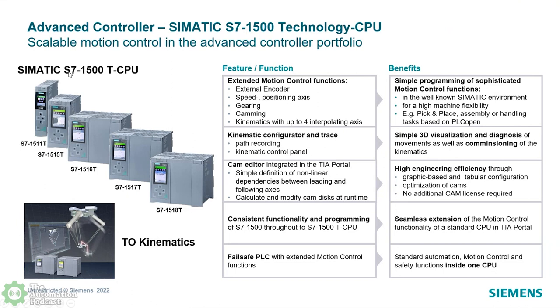For anybody new to Siemens: the CPUs actually get faster the higher up you go — and they get wider. With other PLC brands, you just get more memory, but the CPU doesn't get any faster. With Siemens, they actually get faster. Definitely something to consider for the 1516T and up — space is something you want to look at first. The reason the 1518 is triple-wide is because PROFIBUS is on board; they actually put a PROFIBUS communication card in there, versus the single-wide 1511T which doesn't have PROFIBUS on board, but you can add it.